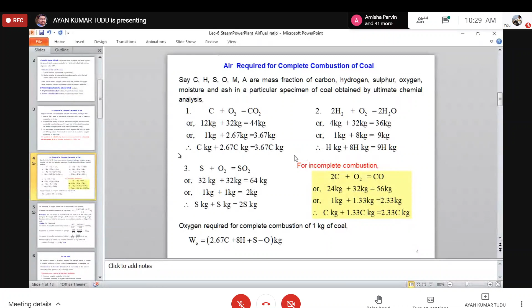Since the percentage of oxygen present in air is approximately 23% by weight, the equation for the air required for complete combustion of 1 kg of coal, WR, equals the above expression for the weight of oxygen divided by the percentage. So the equation comes out to be 2.67 C plus 8H plus S minus O, divided by 0.23.